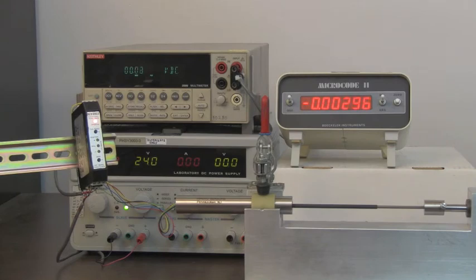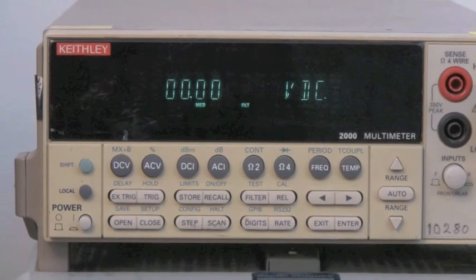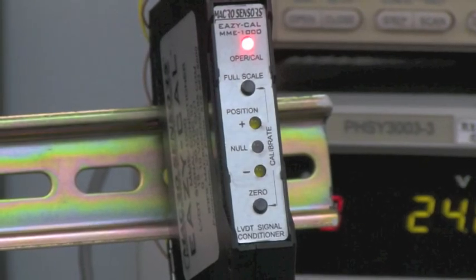Finally, we displace the LVDT back to the zero inch position and we observe the output to be 0.00 volts DC. Calibration has now been successfully completed and the EasyCal is ready for normal operation.